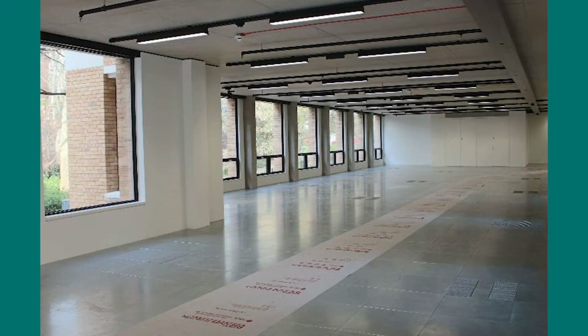One Benjamin selected AET's most flexible system, the CAM-V, which makes use of the raised floor void as a plenum for the distribution of supply air, while receiving return air back to the CAM unit near the ceiling level. With a CAM-V system, there is a considerable amount of flexibility in where the fan tiles can be placed, allowing for easy reconfiguration depending on the particular needs or layout of an office.